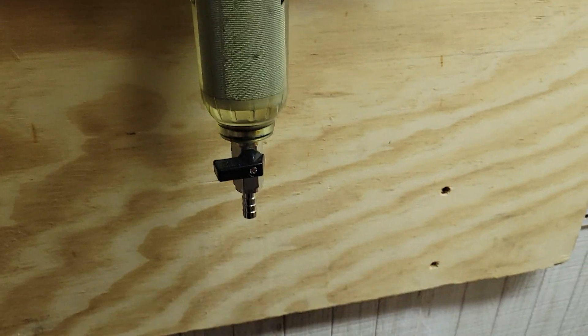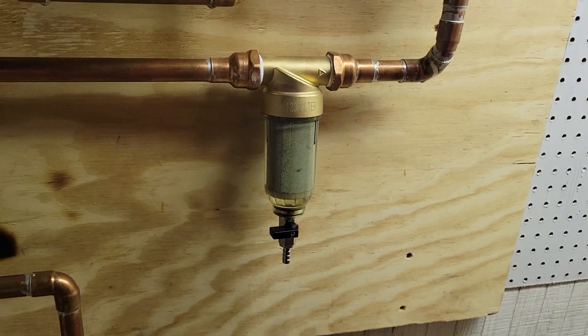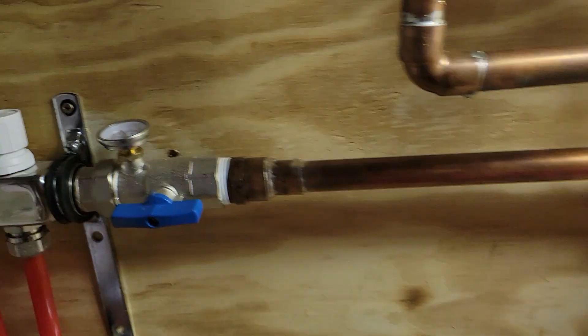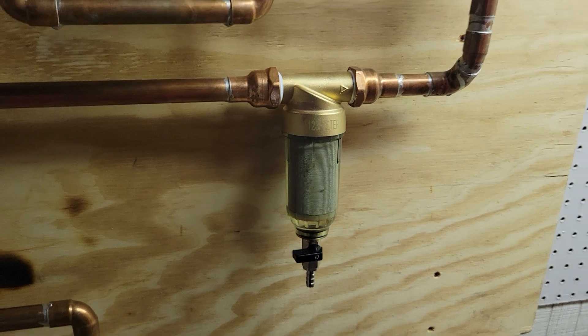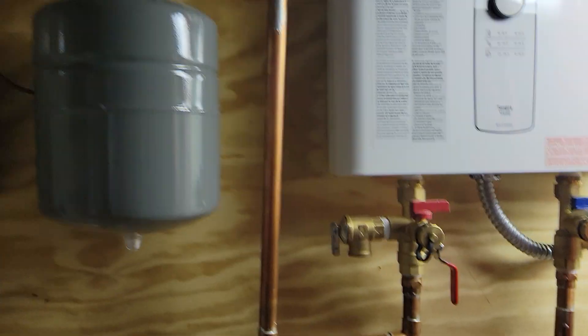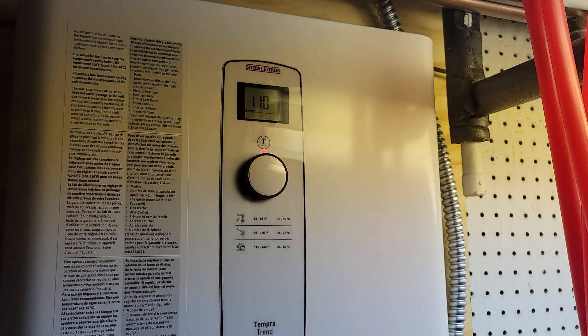The cold water comes through a sediment filter. You can expose the water right there to clean out the filter. It's a bit tough because you need pressure from both sides — I add pressure from my home. It's a closed system but I add a hose and push water from both sides to clean it out. I can also close off and isolate everything, shut it off, isolate this section and clean out the filter. With soldering, anything that pops out would just be captured by the filter.